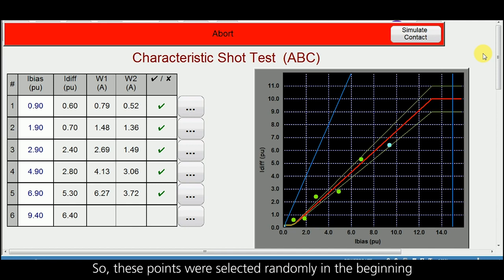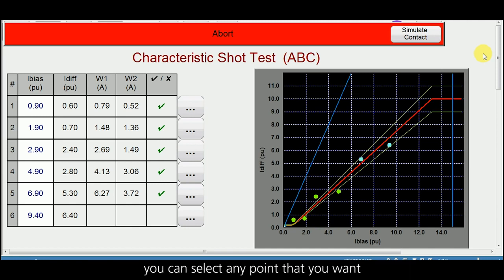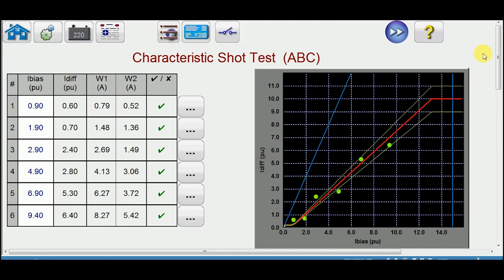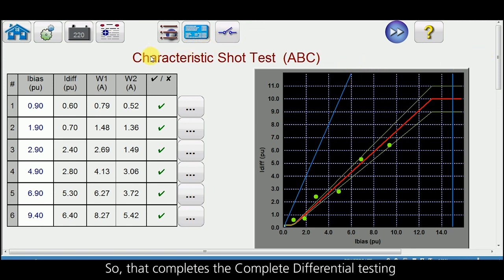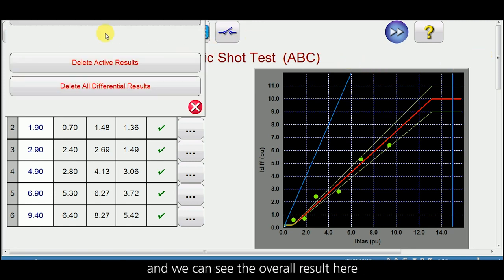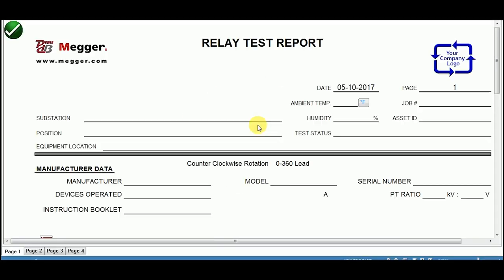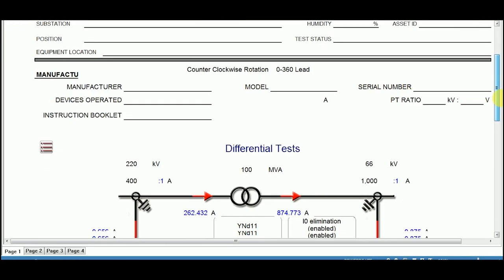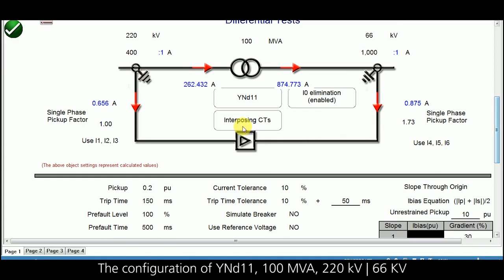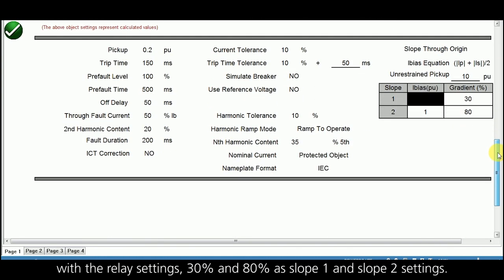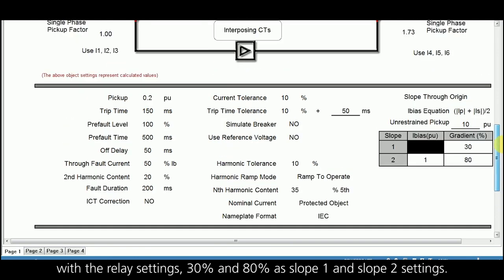These points were selected randomly in the beginning — you can select any point you want. That completes the complete differential testing and we can see the overall result here. The configuration is YND11, 100 MVA, 220/66 kV, with relay settings of 30 percent and 80 percent as slope 1 and slope 2 settings.